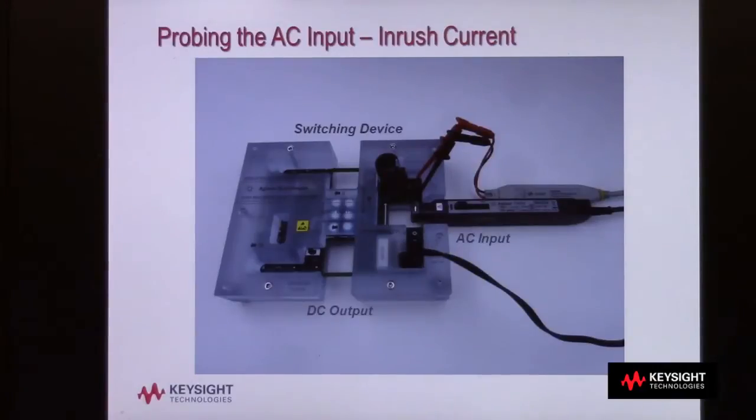The first task in making an inrush current measurement is to probe the AC input with voltage and current probes. You'll typically need a high-voltage differential probe and a clamp-on Hall Effect current probe.